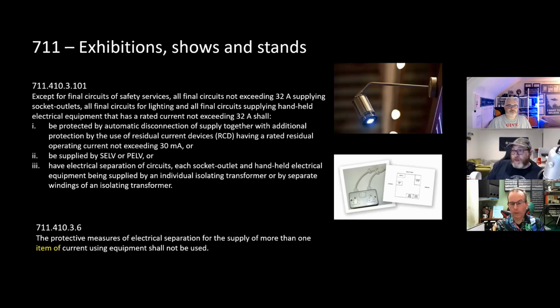The key thing here, this is very similar to a lot of other special locations like agricultural, horticultural, where it says, right, well, those types of final circuits where we can have handheld equipment or low current lighting, they need to have RCDs. It does say the protective measure of electrical separation for the supply of more than one item of current using equipment shall not be used.